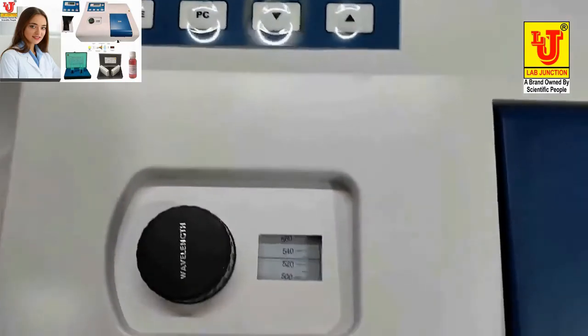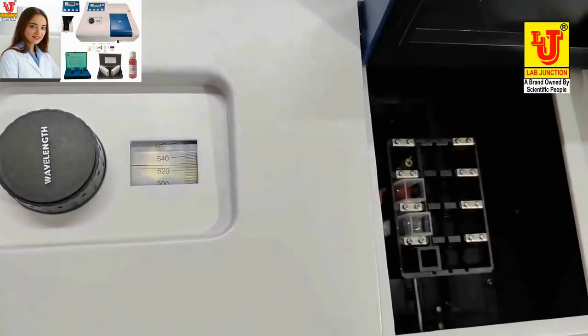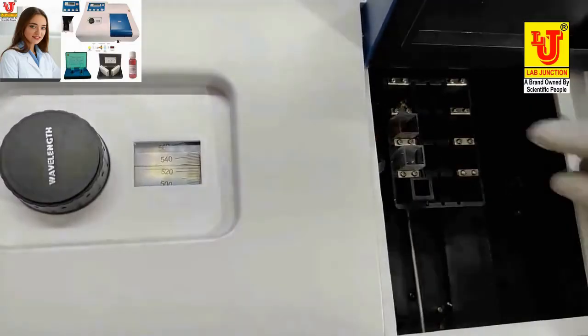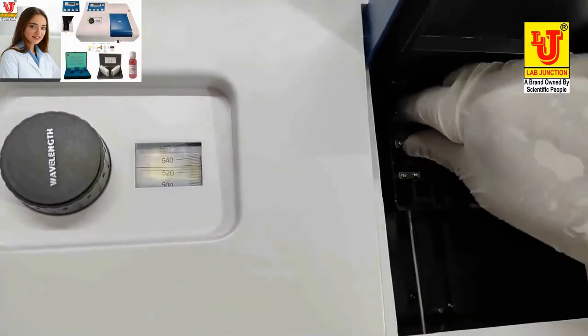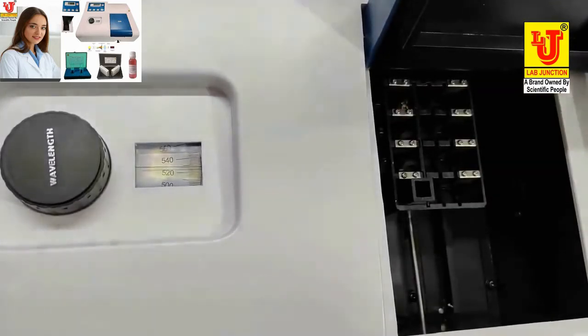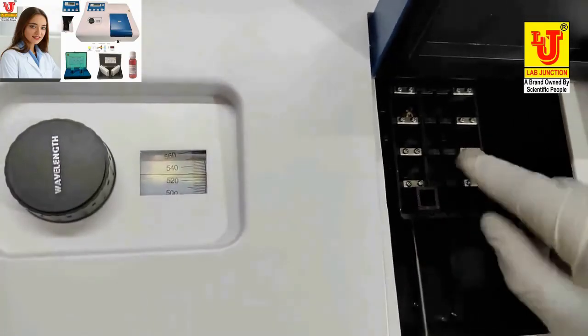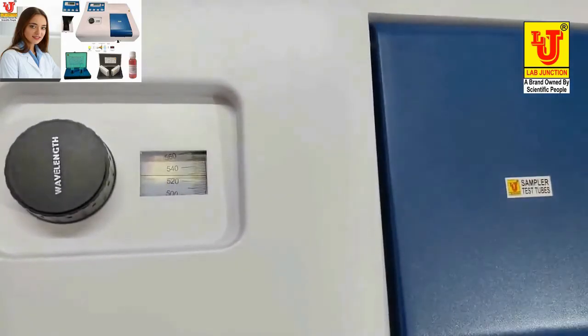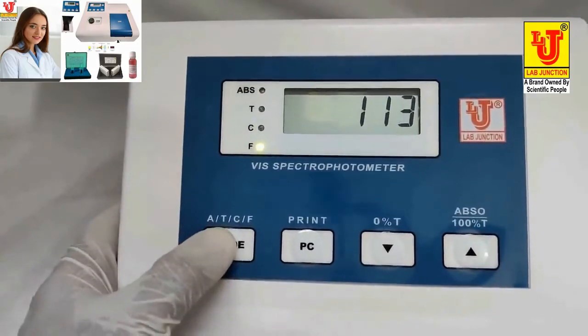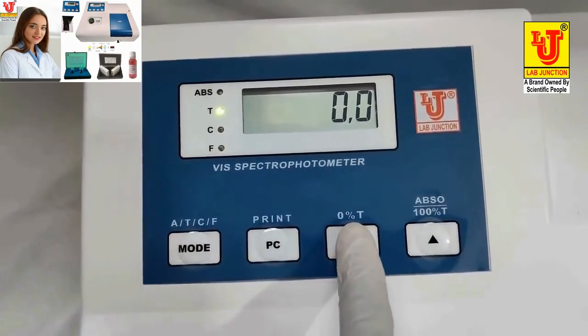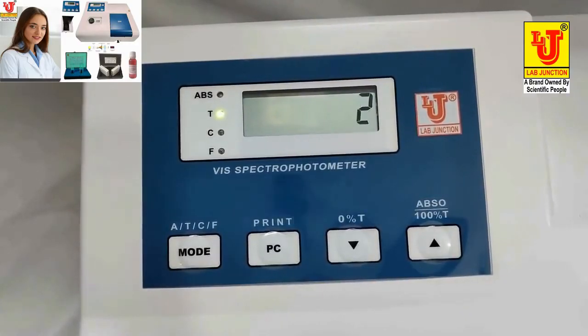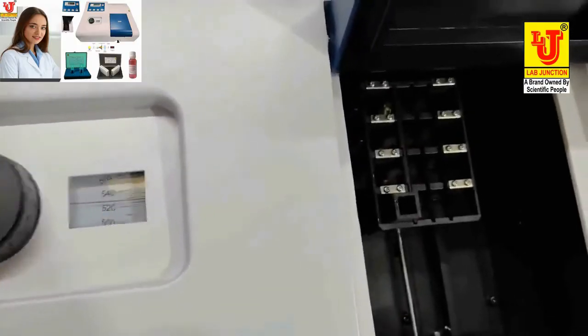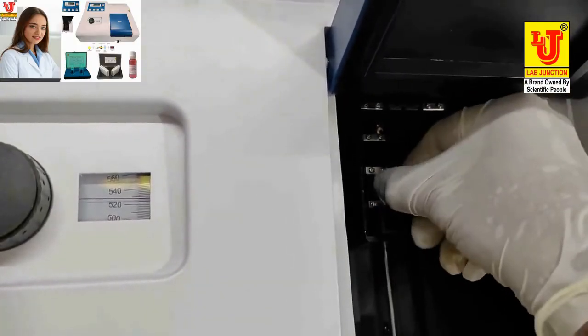Now we are doing the test with the 50 mm cuvette. Removing this. This is the position 1. On position 1, dummy is there. Go to transmission mode. Press 0% transmission for preset 0 or dark current, like this way. Now I am removing this jack.